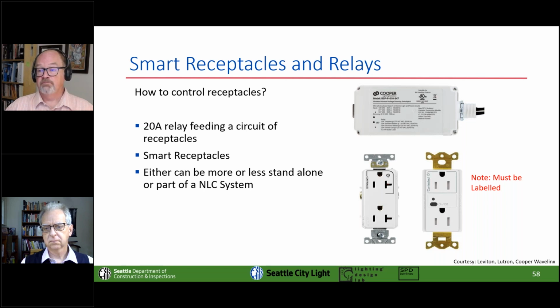You'll note that one half of it is controlled, one half of it is not controlled. So really all you have to worry about is just putting the thing in the wall, and it works out just fine. Now, another thing that I will point out is that these things have to be labeled as controlled. So yes, if you're in the classroom and you plug your aquarium into the controlled portion of the outlet, that could be a problem. Which isn't to say that it's always going to be labeled, but it's supposed to be labeled. So, all right, that's it.